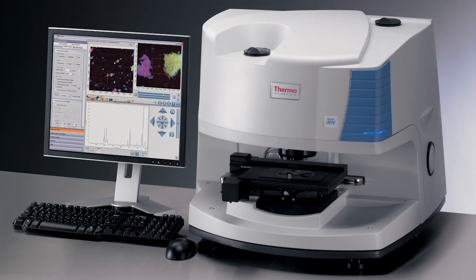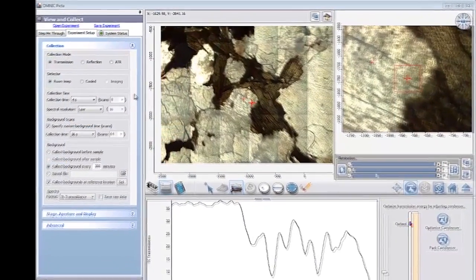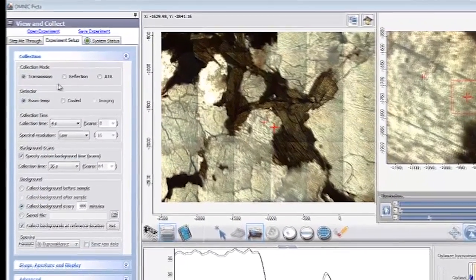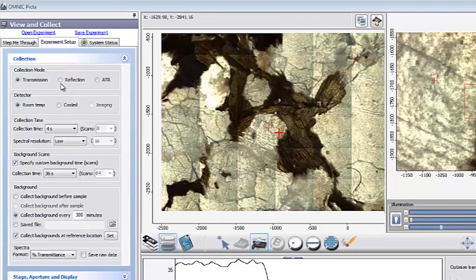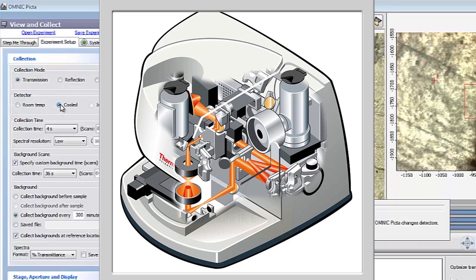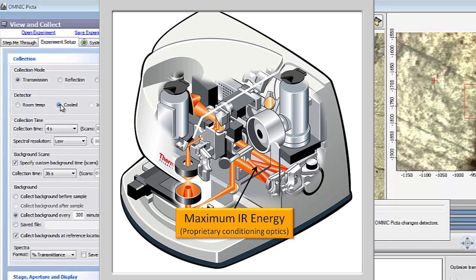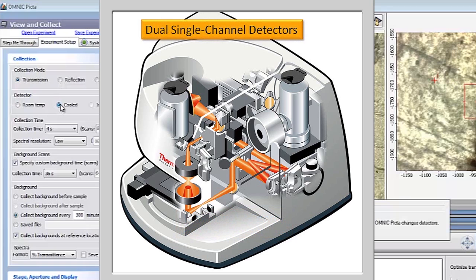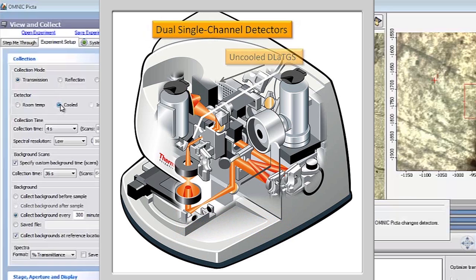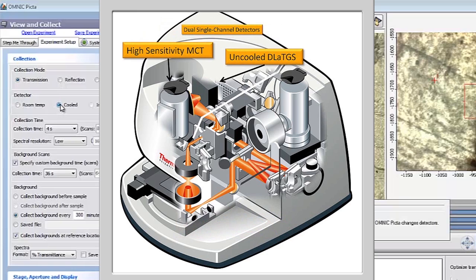While designed for streamlined operations, experimental flexibility remains a priority. All sampling modes – transmission, reflection, and micro ATR – produce results with truly outstanding performance. The integrated spectrometer is optimally coupled to the microscope for maximum throughput, allowing operation with a standard uncooled detector. The fast and very sensitive MCT detector is a popular option.